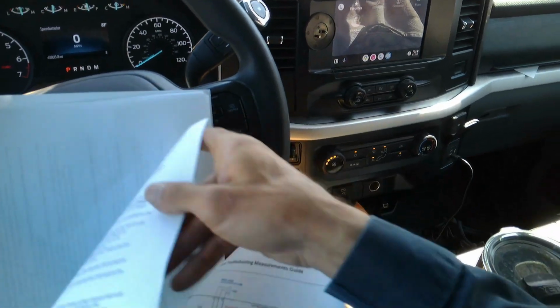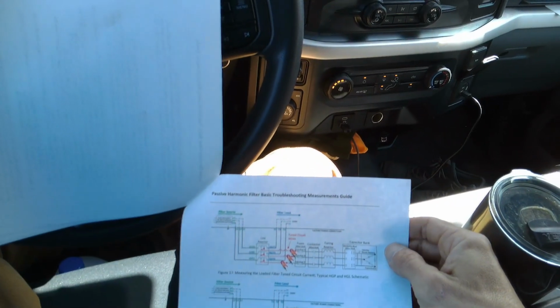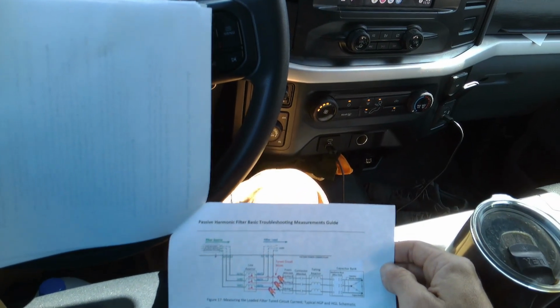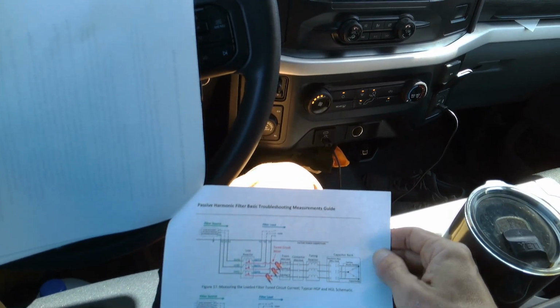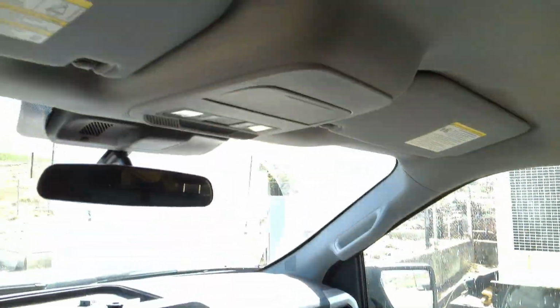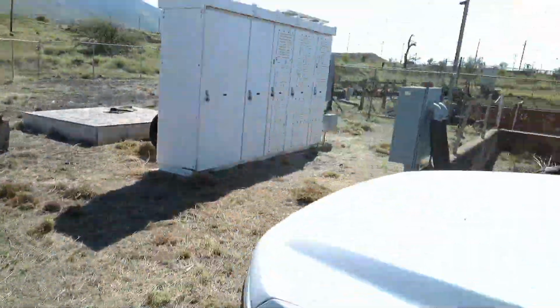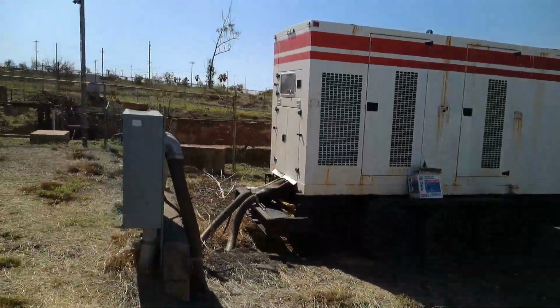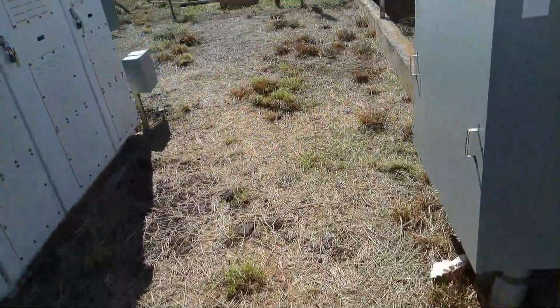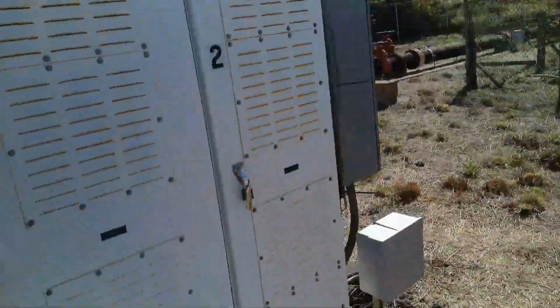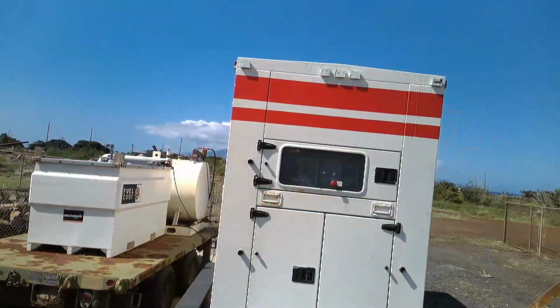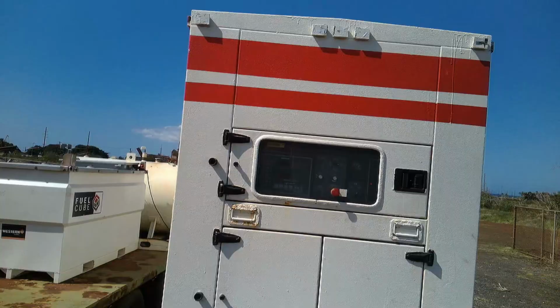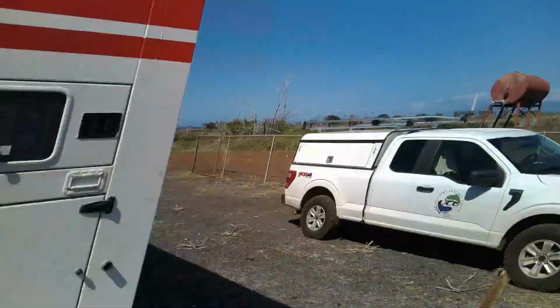Tuned circuit current, good. Tuned circuit wires, yeah, okay. Interesting. Okay, pretty straightforward. We'll shut down, check all our fuses and capacitors. Then after we've checked all the fuses and capacitors, we'll power up and do our load and no load testing. Voltage is good, 480.